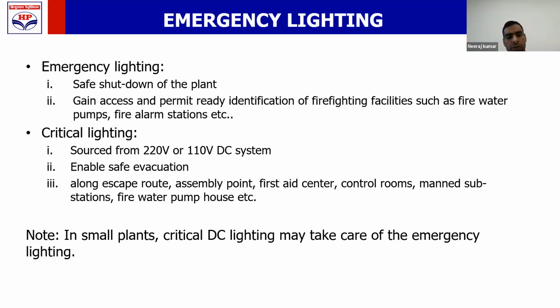In case of small plants, maybe at marketing locations where you may not have an emergency DG, then in place of emergency light, you can use DC critical lighting for the entire plant because your plant is very small. So you may have only normal lighting and DC critical lighting. You may not have emergency lighting, but the DC lighting should be able to serve the purpose of safe shutdown and access to firefighting equipment.